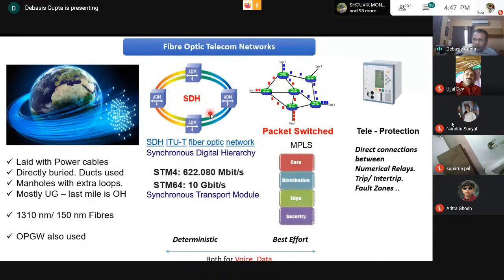But in Calcutta what we are doing is we are using SDH. So the moment the signal comes that the station has tripped, it comes to SDH, and within at most 75 milliseconds, matching load is tripped across Calcutta, not in one place, but in different places.